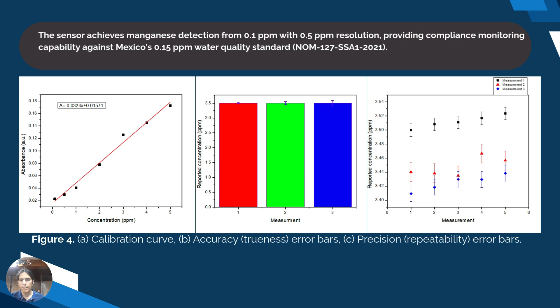In the first image, we can see the calibration curve, in which the points were 0.1, 0.5, then 1 ppm, 2 ppm, 3 ppm, 4 ppm, and finally 5 ppm. The next image shows three measurements made, and we can see that the absolute error doesn't vary too much. It is close to 3.5 ppm, and this gives a good estimation for field use. The last graph was of the same three measurements and gives precision or repeatability error bars. On average, the standard deviation is 0.01389, and this is mostly limited by electrical noise.